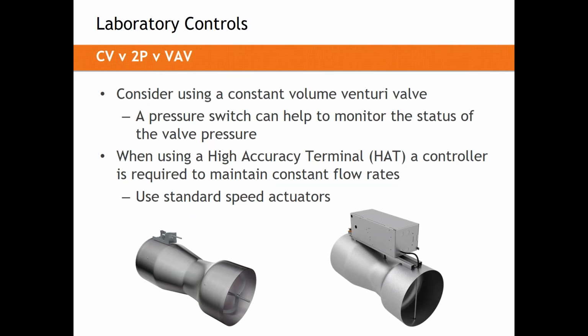If you're using a high accuracy terminal for equipment control, so thinking, biological safety cabinet, snorkels, things like that, I do not mean fume hoods, you should consider using standard speed actuators whenever possible. Remember, a high accuracy terminal is a closed loop device. It is always measuring and controlling. Measurement and control is always easier to do at a slow speed. Regardless of the manufacturer or the type of device, it's easier to do when it's slower.